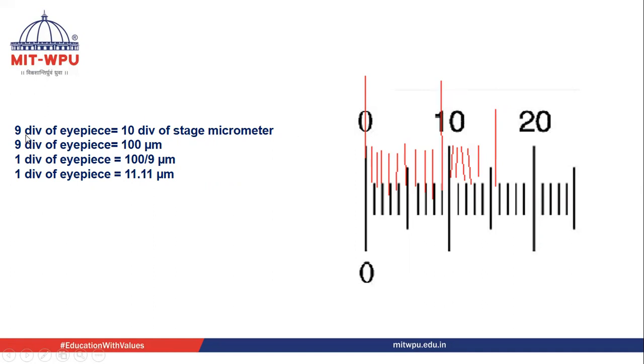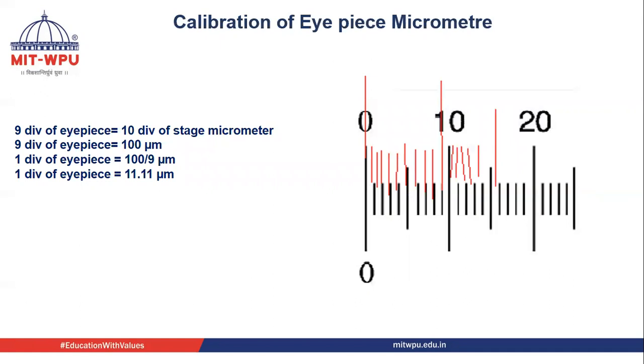So we have found that 9 divisions of the eyepiece micrometer equal 10 divisions of the stage micrometer. Ten divisions of the stage micrometer equal 100 micrometers (since one division = 10 micrometers). Therefore, 9 eyepiece divisions = 100 micrometers, so one eyepiece division equals 100 divided by 9, which is 11.11 micrometers. This is our calibration factor, and we must remember it.